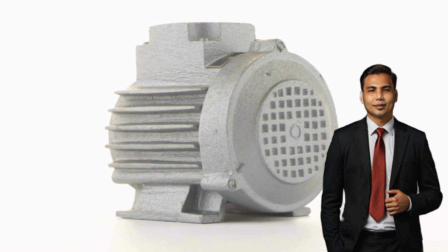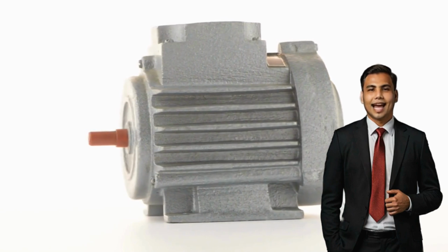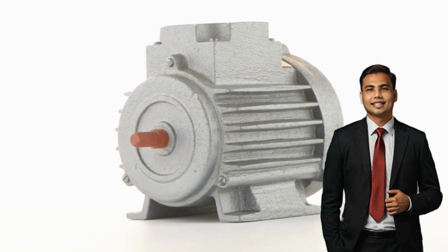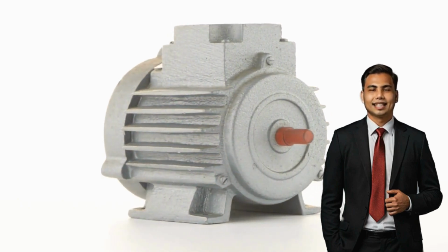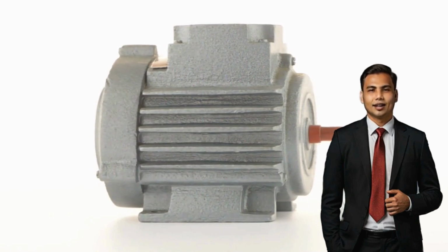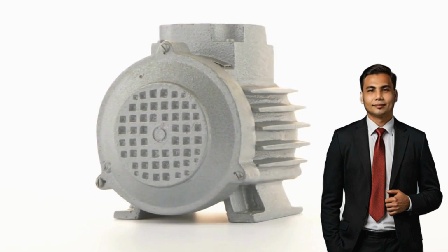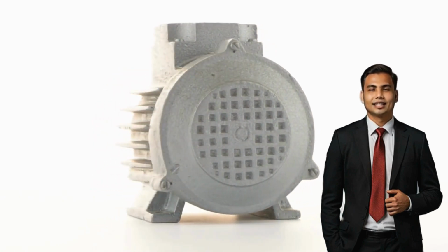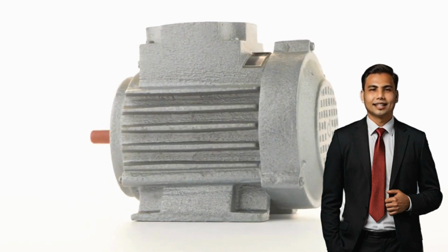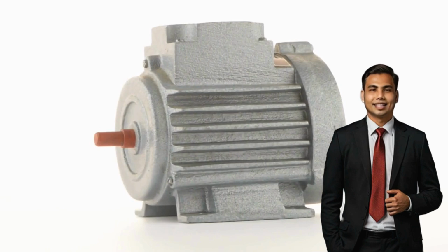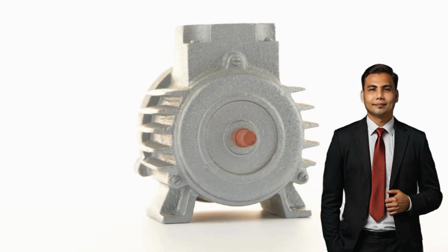The basic design of a three-phase squirrel cage induction motor consists of two main parts, the stator and the rotor. The stator is the stationary part of the motor and consists of a core, made of thin, laminated silicon steel sheets to reduce eddy current losses. The stator core is essential for supporting the magnetic field generation. Windings: the stator contains three sets of windings spaced 120 degrees apart from each other. These windings are made of copper wire and are placed in the stator slots. When a three-phase power supply is applied, the windings create a rotating magnetic field.